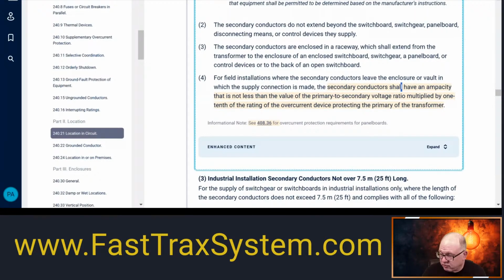So in this case, those conductors have to be rated what? The primary to secondary voltage ratio multiplied by 1/10 of the overcurrent device. So there was a 200 amp overcurrent device on the primary. I'm just throwing out numbers. So it would be 2.31 multiplied by 20, and that is 46.2 amps. So those secondary conductors shall have an ampacity of not less than 46.2 amps. You're probably going to have much more than that.